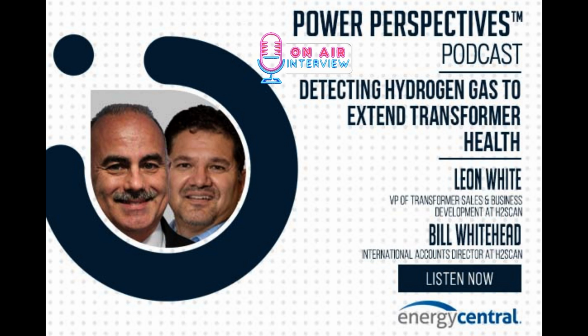Fast forward the last 5 years or so, I call it the disruptor scenario, where the GridScan 5000 was developed: hydrogen specific, 10 plus years of life expectancy, with continuous accurate information that can be installed on a single valve practically anywhere in a transformer. What changed over this multi-decade journey was the life lessons of online gas monitoring systems, the true life expectancies of these units, and the maintenance costs. Then the disruptor came out, solving the problem with long life expectancy from a hydrogen sensing technology that can be deployed on pretty much any size transformer because of its low price point.